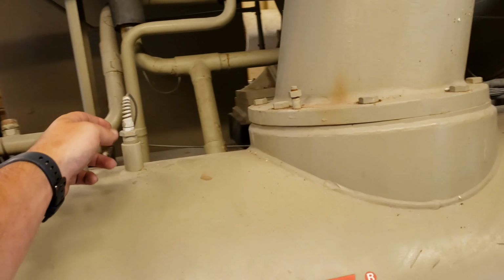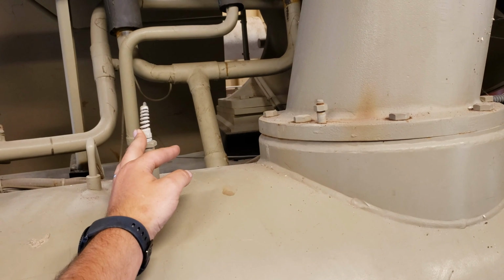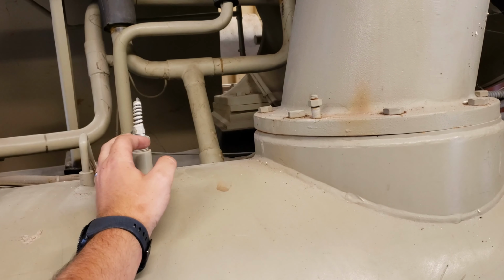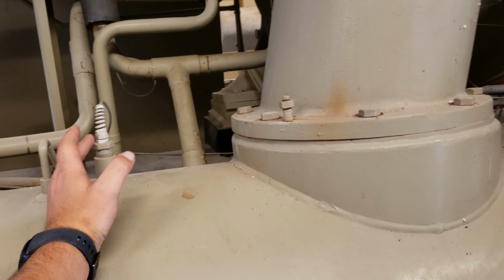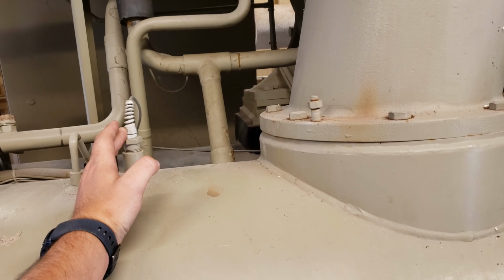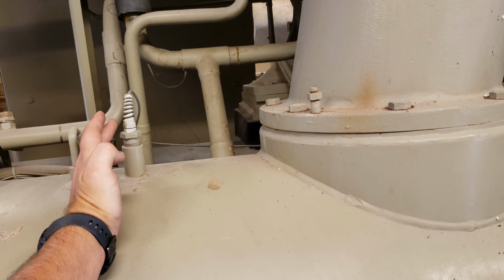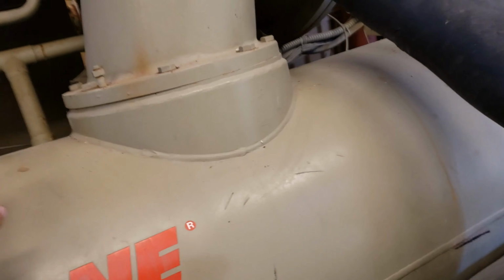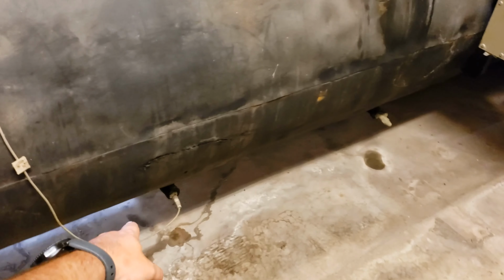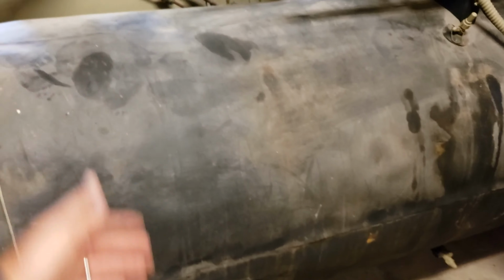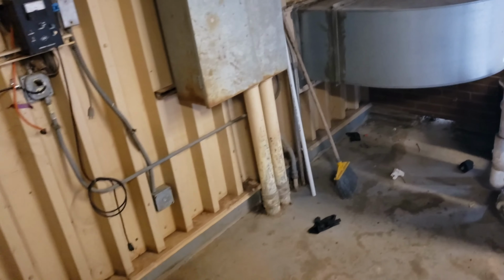saturation sensor. And keep in mind, with these Tranes, I rarely ever see them with actual transducers on the barrels. They use temperature sensors for saturation. They have one there on the condenser, and then there's one down here on the evaporator, and that is what it's using to actually determine what the system pressure and operating status is.